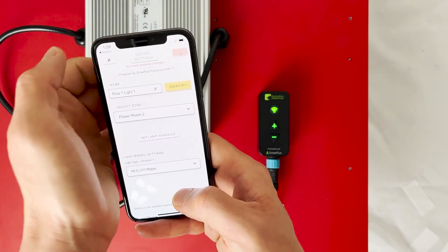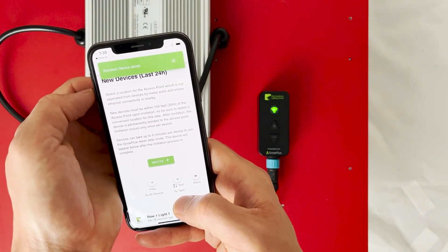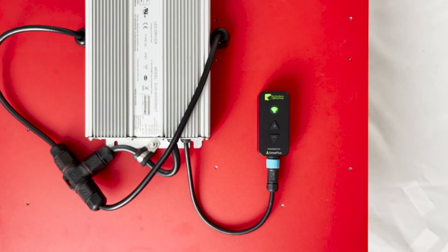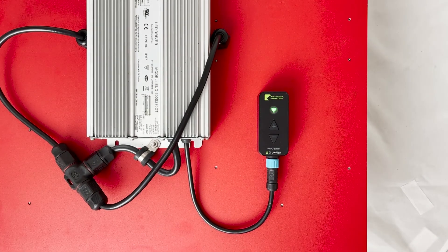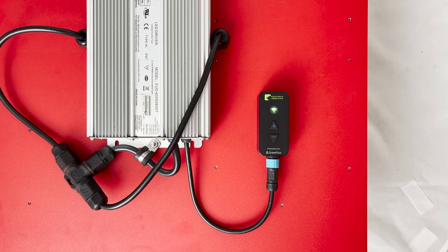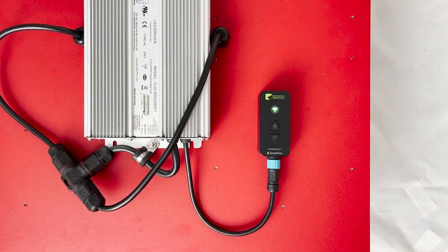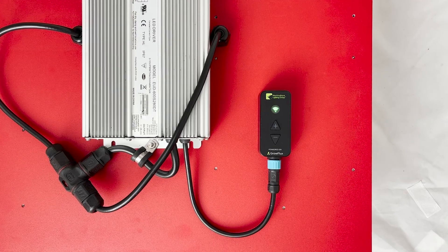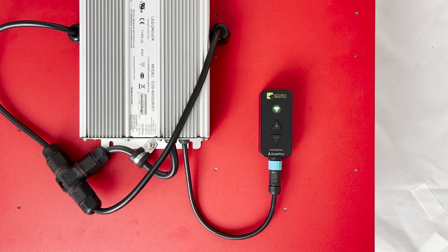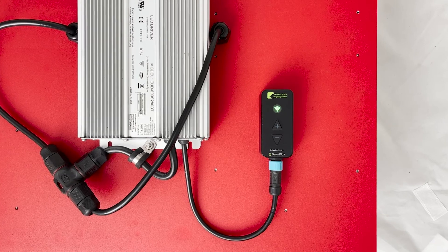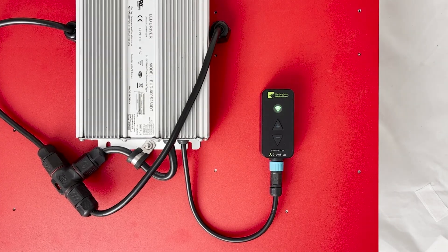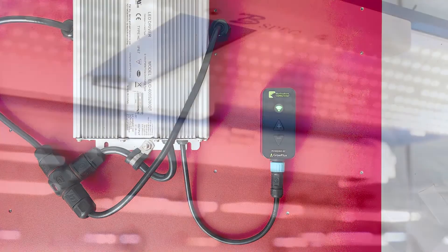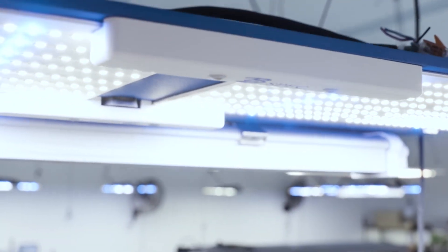You will notice that the indicator lights on the buttons to the wireless adapter just turned off. This means that the light has been assigned to the zone, and any lighting schedules on that zone have been applied to that light. Once lights are zoned, the manual control buttons are disabled. However, these buttons are automatically re-enabled if the light ever loses its mesh connection, if the access point is unplugged, or if the access point loses internet connectivity.